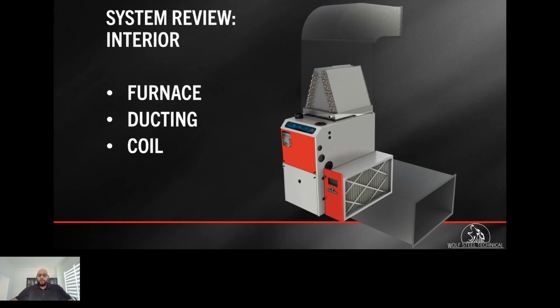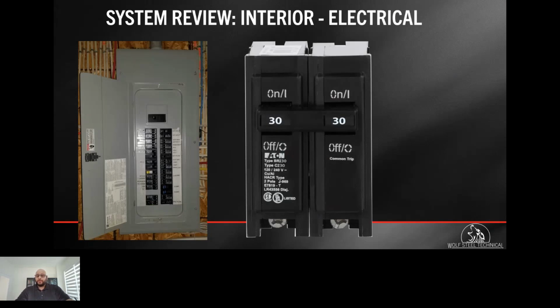You're going to want to take a look over the breaker panel. Any work that's been done in a breaker panel should be done by a licensed electrician. What kind of breaker does the panel take? Is there enough space for another double pole breaker? Is it a 100 amp or 200 amp panel? Based on the electrical code, you will determine what gauge wire you're going to be running from the panel to a disconnect. You're also going to want a minimum of a 4-conductor thermostat wire from the indoor unit to the heat pump, and a minimum of a 6-conductor thermostat wire from the furnace to the thermostat if you're planning on running a one-stage heating and cooling.